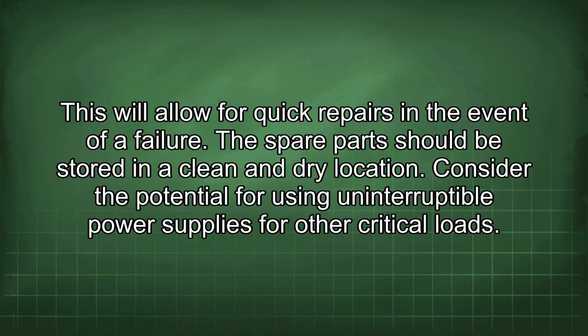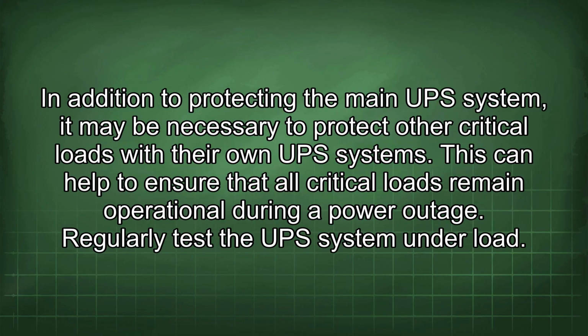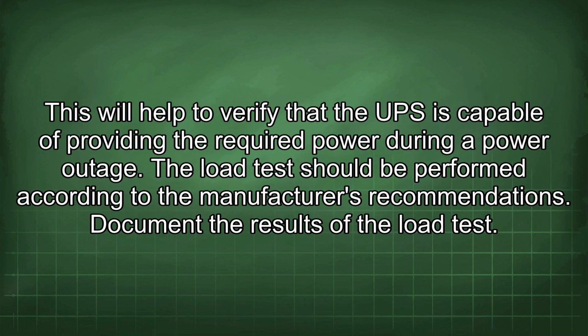Consider the potential for using uninterruptible power supplies for other critical loads. In addition to protecting the main UPS system, it may be necessary to protect other critical loads with their own UPS systems. This can help to ensure that all critical loads remain operational during a power outage. Regularly test the UPS system under load. This will help to verify that the UPS is capable of providing the required power during a power outage. The load test should be performed according to the manufacturer's recommendations. Document the results of the load test.